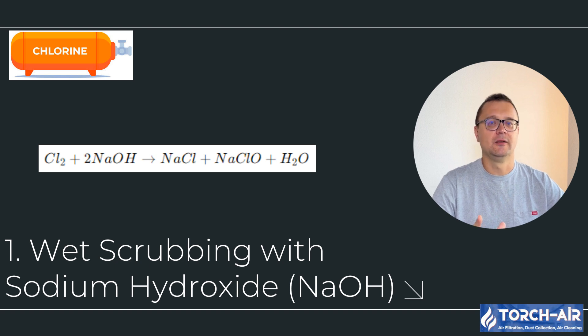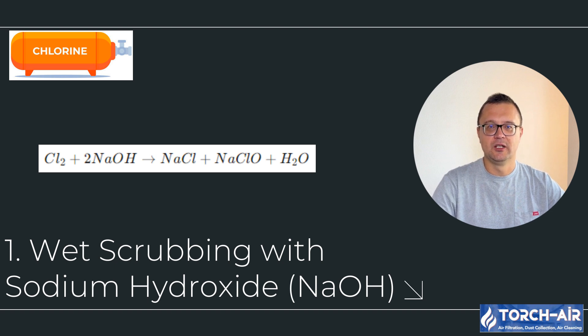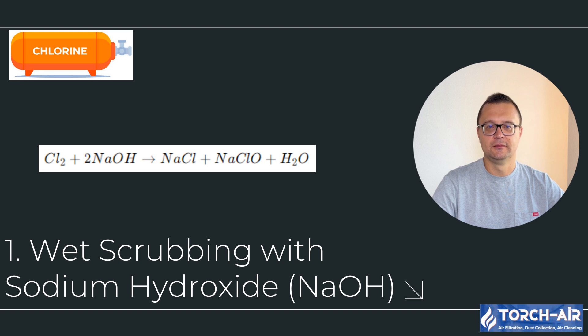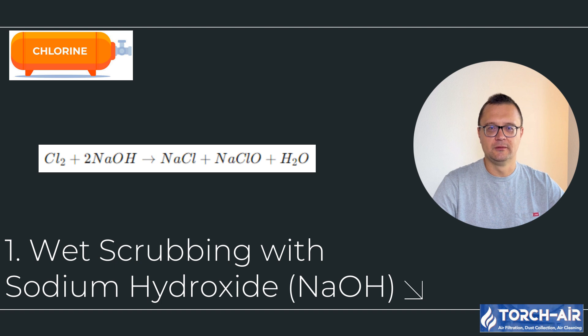Neutralizing chlorine gas typically involves chemical reactions with alkaline substances that convert the chlorine into less harmful byproducts. The two main neutralization techniques used in scrubber systems are: first, wet scrubbing with sodium hydroxide (NaOH). This is the most common neutralization method for chlorine gas. The NaOH solution reacts with chlorine gas to form sodium chloride (NaCl) and sodium hypochlorite (NaClO) — much safer compounds. Contaminated air is passed through a scrubber where it meets a sodium hydroxide solution, converting chlorine into salt and water. Best for continuous industrial applications with consistent chlorine gas emissions.